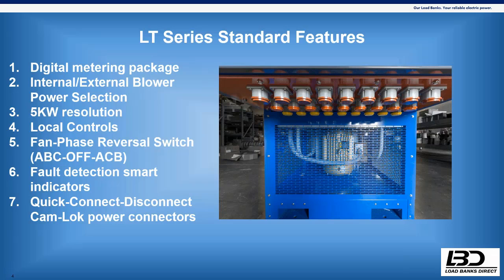We also offer internal and external blower power selection. So you can either derive all of the power required to drive the fans right off the bus inside the load bank, so off of the generator that you're load testing, or you can go to external and get that power from an external source. Some of you might be wondering what the pros and cons are. It really just depends on the load test and what's going on, because the blowers obviously draw power. So say you've got a 1 megawatt load bank and you're load testing a 1 megawatt generator. If you throw all the switches on, you're putting a meg on it with the load bank, but if you're deriving your blower power internally, you're actually going to be drawing more than 1 megawatt, because the 1 megawatt rating doesn't take into account the power being drawn by the blowers. So that's a feature we offer on all of our trailer mounted gear as well.